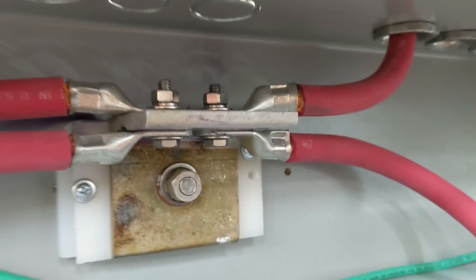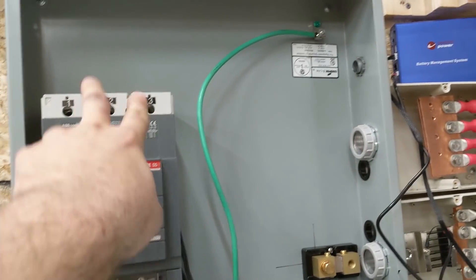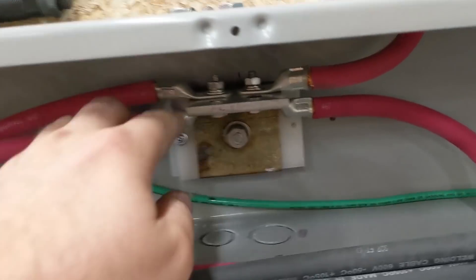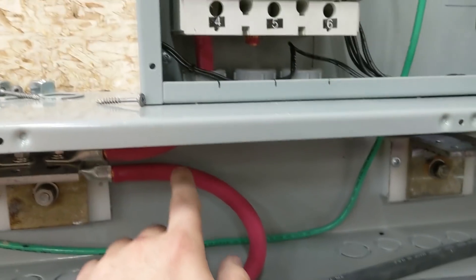I'm going to spray them down with some more. If anybody would prefer that I replace my DIY bus bars with commercially available units, please leave a link in the description below to bus bars that are specifically rated for 300 amps continuous, 48 volts DC minimum, and they must be UL listed for residential use. I actually found this list of requirements to be quite difficult to track down.